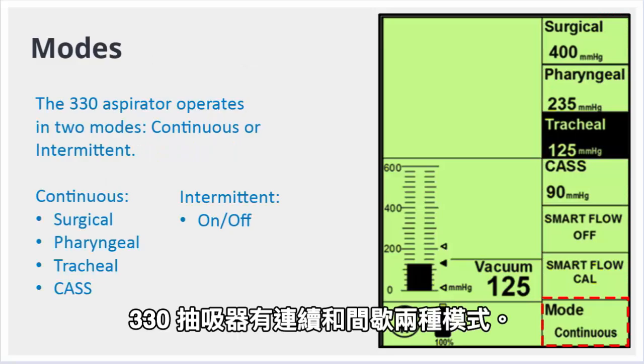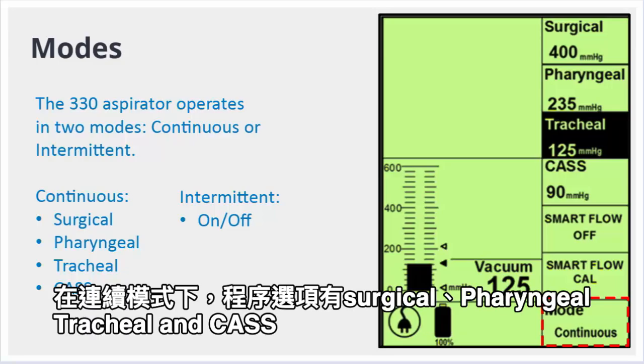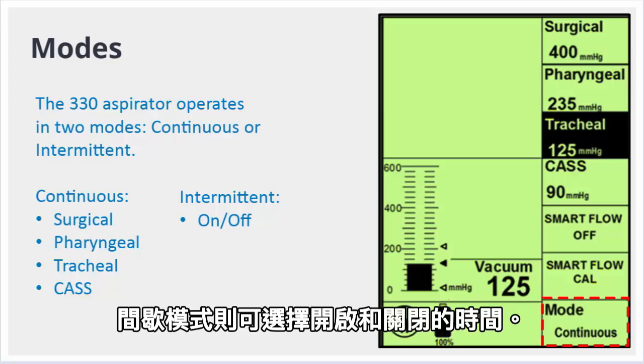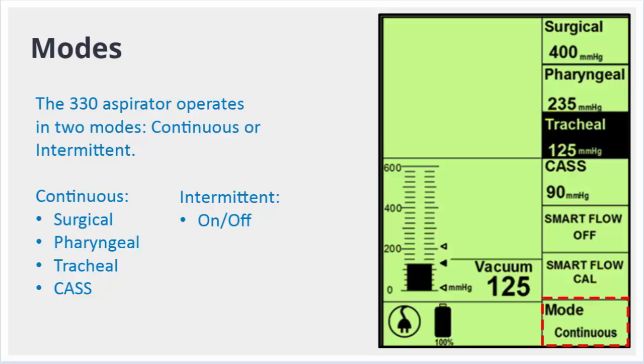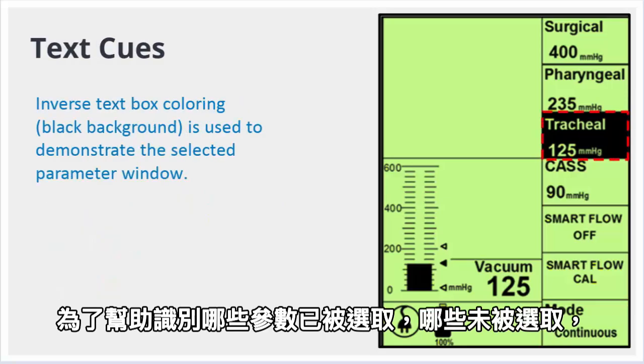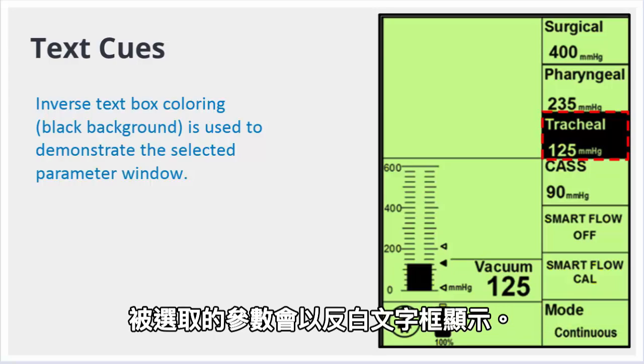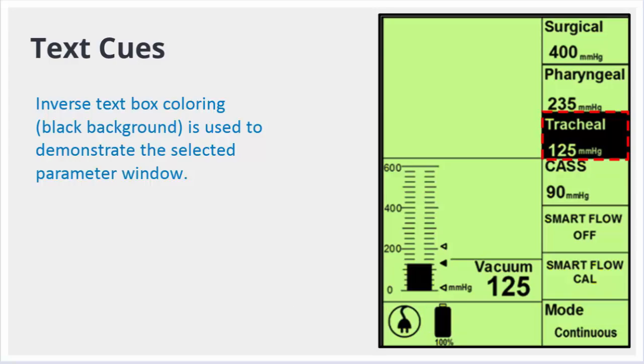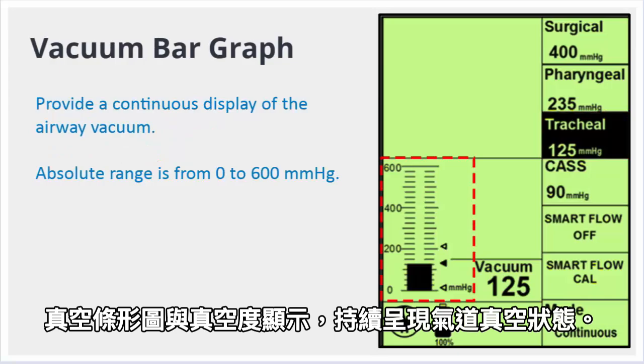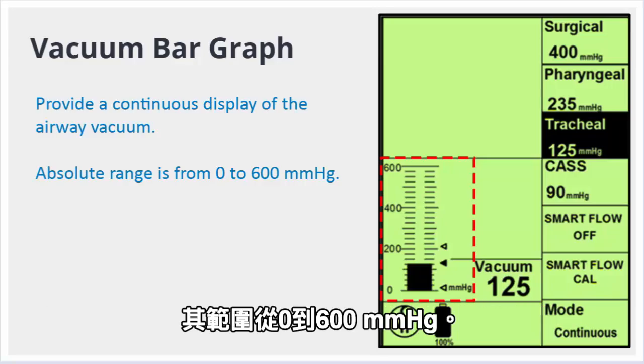The 330 aspirator operates in two modes, continuous or intermittent. In continuous mode, the procedure options are surgical, pharyngeal, tracheal, and CASS. Intermittent mode provides the ability to select the on and off timing. To assist in recognizing parameters that are selected and those that are not, the selected parameter window will be indicated by inverse text box coloring. Vacuum bar graph and vacuum level measurement provide a continuous display of airway vacuum. Its absolute range is from 0 to 600 millimeters of mercury.